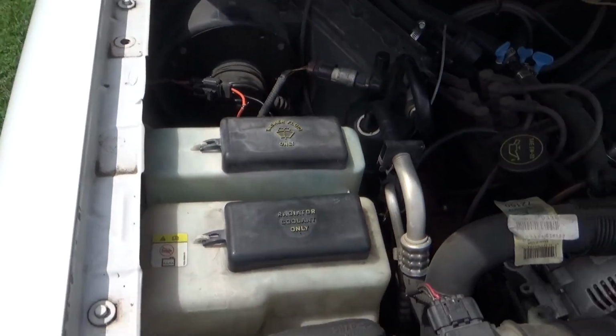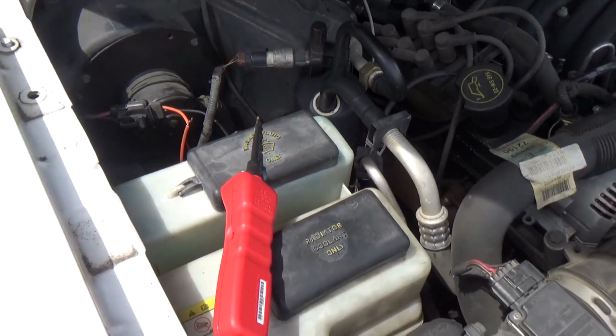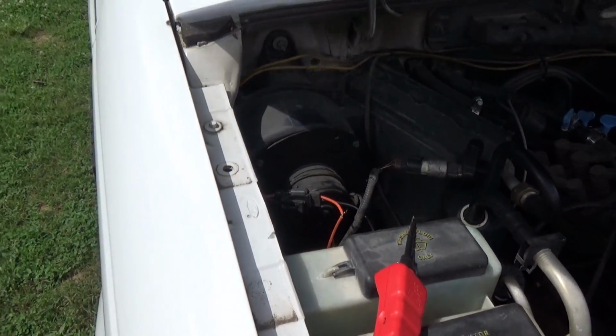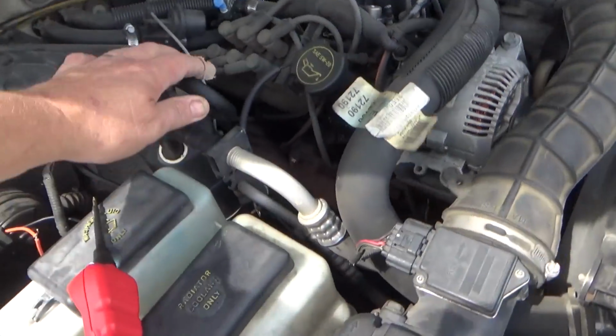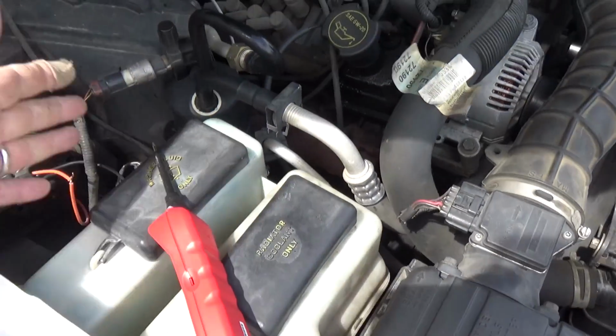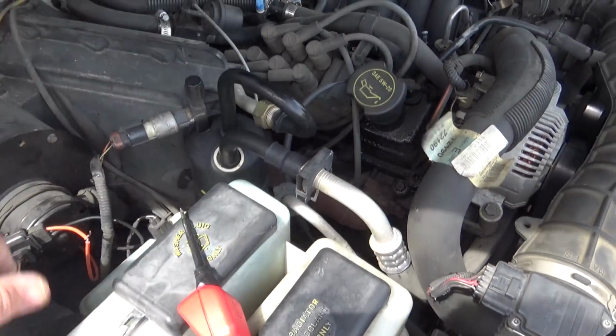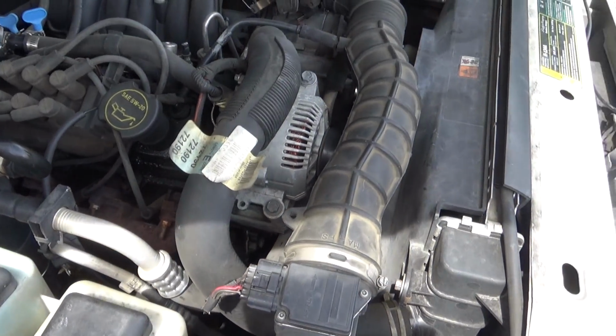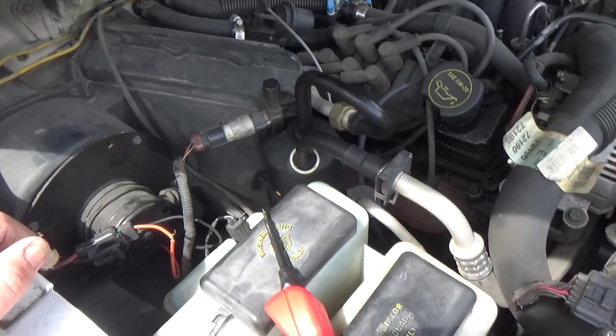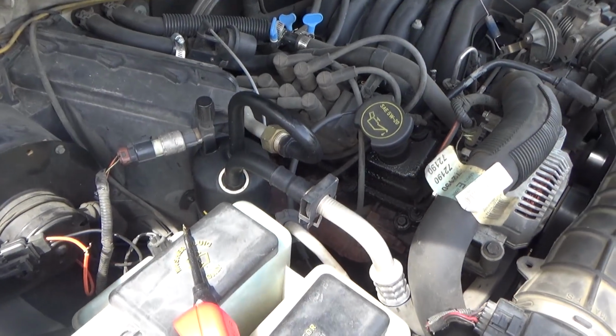The first thing we're going to do is fire it up and see if we're getting any power at the fan or the relays. The compressor's running, this is good and cold, but there's no air blowing across it, so it's going to go up high and then it's going to kick back off. You can hear it clicking in and out because there's nothing pulling the cold air out of the system.